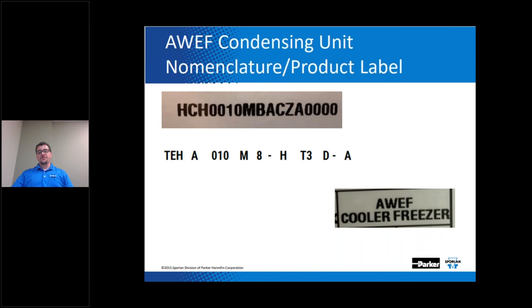AWEF-compliant condensers will specify AWEF on the equipment label — I'm showing you a picture of that label in the bottom right corner. Non-AWEF units, manufactured prior to AWEF becoming law, likely have a higher low ambient head pressure setting than these AWEF-compliant units.